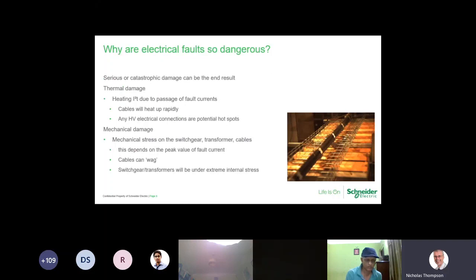So when we start to look at why we need protection, electrical faults can be really dangerous. When we look at cables, transformers, switchgear, when we ramp up the currents, we're ramping up the heating effect, because cables, copper and aluminium are basically just big resistors, albeit that the resistance values of copper and aluminium are very, very low. That's why we use them as conductors. But they are basically going to create a big heater. So anything within an HV switchboard or a transformer where you've got connections or wires in close proximity to each other is potentially going to create hotspots.